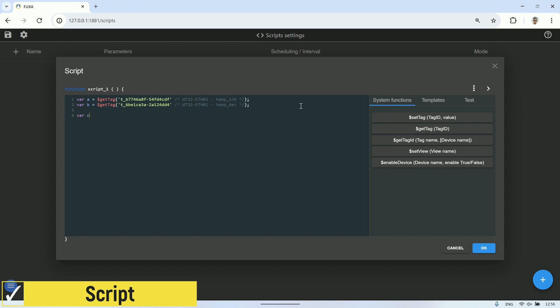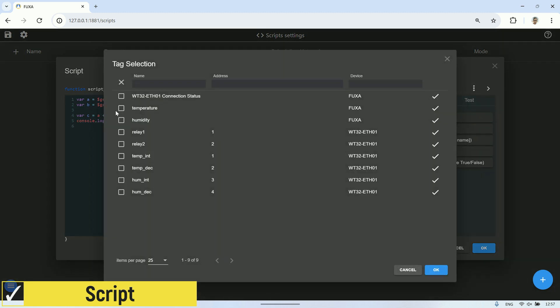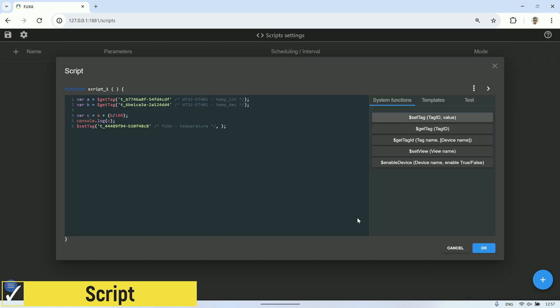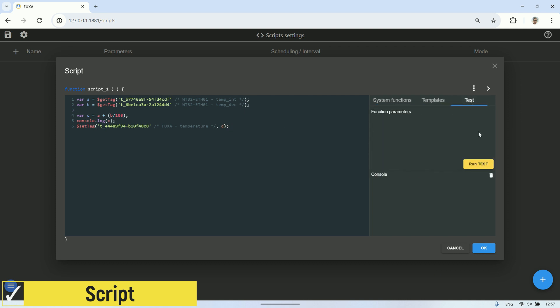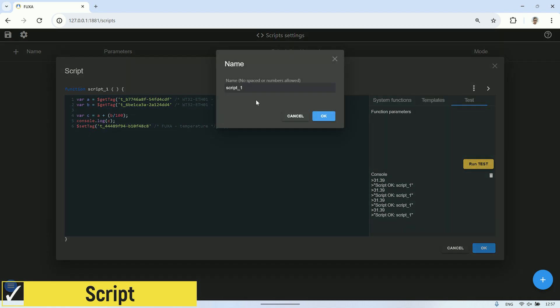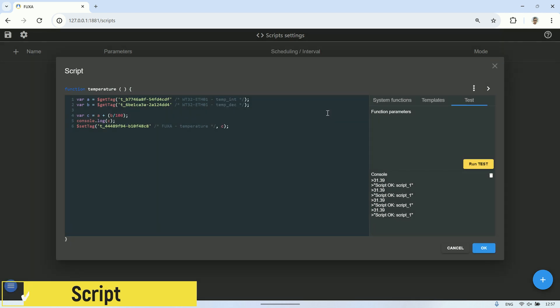Writing code in the script is quite straightforward since it uses JavaScript. In this script, I retrieve value A from the tag representing the integer part of the temperature, and B represents the decimal part. Then, I combine them into value C. Next, I'll set the temperature tag on the server with the value of C. We can test the script we've created by clicking on the test tab on the right side, then clicking run test. If there are no errors, the values we've displayed using the console.log syntax in the script will appear. Click on edit script name to change the script's name. In this example, I'll change the name to temperature. Next, create a script for the humidity value using the same steps.